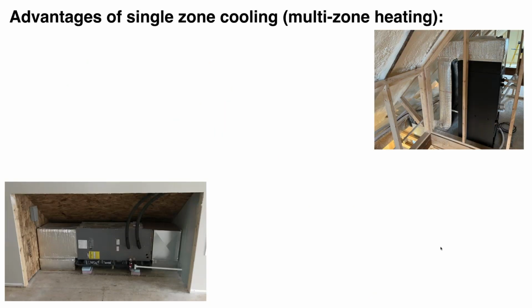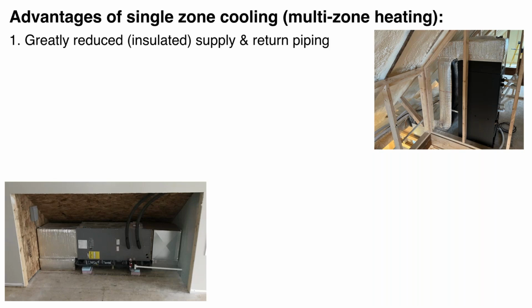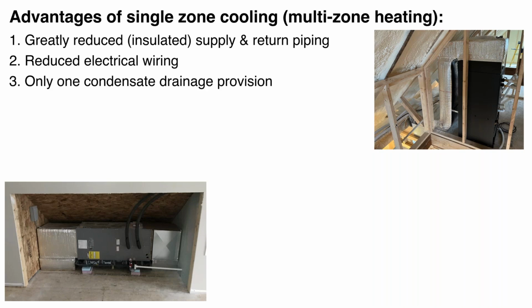Now, I tend to like single zone cooling combined with multi-zone heating. So again, here's some examples of air handlers. These are whole house air handlers. This one is installed in a house that has spray foam up against the underside of the roof deck. So that entire space is within the thermal envelope of the building, which is nice from the standpoint of running ducting and minimizing losses. So the advantages of single zone cooling greatly reduces the insulated supply and return piping, as well as condensate drains, wiring, and so forth.